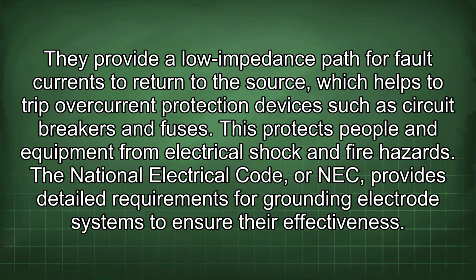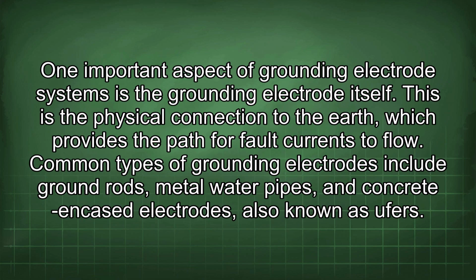They provide a low impedance path for fault currents to return to the source, which helps to trip overcurrent protection devices such as circuit breakers and fuses. This protects people and equipment from electrical shock and fire hazards. The National Electrical Code, or NEC, provides detailed requirements for grounding electrode systems to ensure their effectiveness. One important aspect of grounding electrode systems is the grounding electrode itself. This is the physical connection to the earth, which provides the path for fault currents to flow.